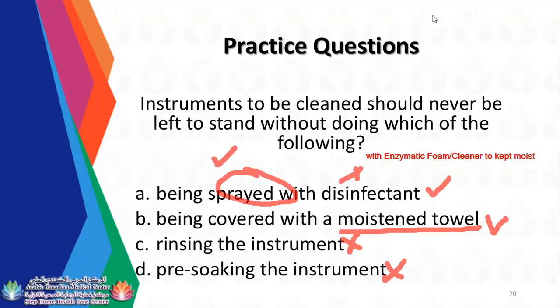So instruments to be cleaned should never be left to stand without being covered with a moistened towel. Prolonged delays in cleaning can have a detrimental effect on the instrumentation. Sets can begin to stain, pit, rust, and become dull. Dried blood becomes more difficult to remove. Some devices cannot be submerged and must be cleaned manually.